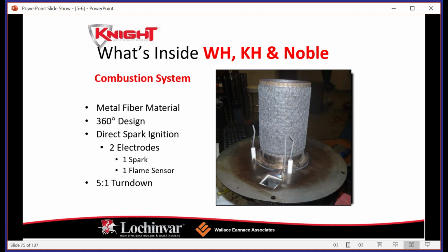The reason that we use a metallic fiber material is to create a lower temperature flame to create the same BTU input. And the reason we want a lower temperature flame is, A, stress on the product's wear and tear, but also something called NOx compliance, NOx, right? NOx is regulated depending on where you are in the country, either not at all, or in some parts of the country very strictly. So if anybody's calling in from the West Coast, you are well aware of your NOx compliance. Utah, again, they've got big cities in the valleys down there, and it's very important that NOx compliance is there.